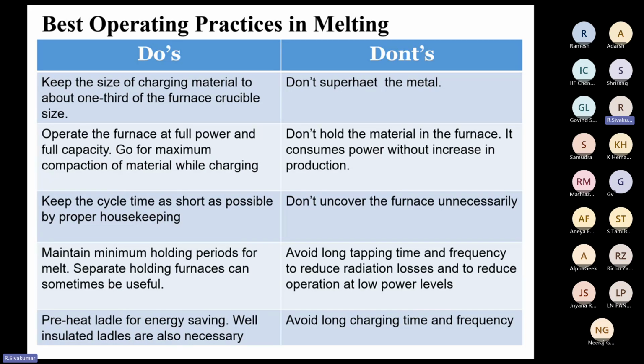Practically, in the many energy audits and energy studies we have conducted in foundries, the first thing we noticed is that longer holding times take more power. Ideally, for any furnace manufacturer like Inductotherm, and the majority of furnaces are Inductotherm, as per the OEM recommendation, one melting cycle should be completed within 45 to 50 minutes. But practically, it ends up taking 70 or 80 minutes.